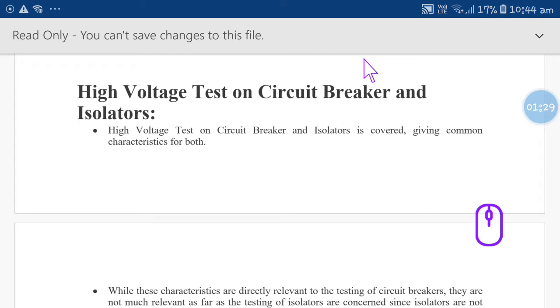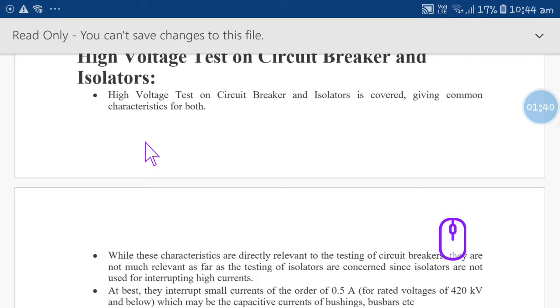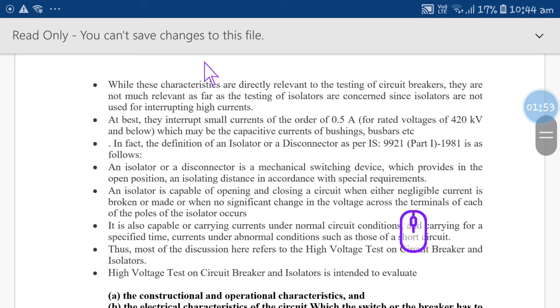Now we have to do testing of these. Once testing of circuit breakers and isolators is done, it means they have that much withstanding capacity. Then after quality testing they will be erected in the field. High voltage testing has to be done on both the isolator and the circuit breaker, and you can consider that common characteristics apply to both. Before going further, I am going to give some points on this.